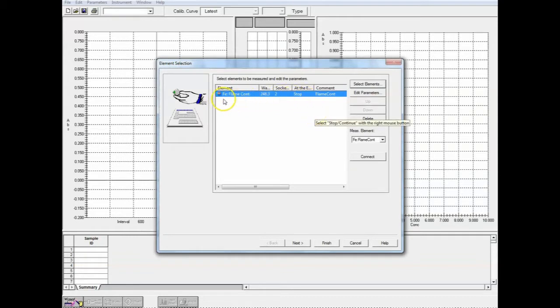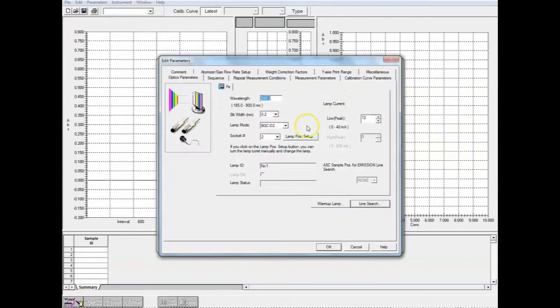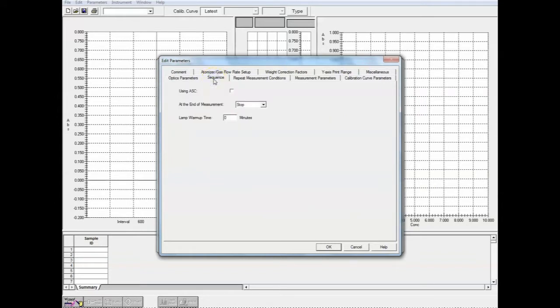So we've selected our element. You can see right here it says iron flame, ready to go. It gives you the wavelength as well. Then we're going to select edit parameters, and that's where we're going to put in the rest of the information about our method. This is where we would be able to change any of the default settings that I showed you previously for the iron lamp. That's all preset. We generally don't need to change any of these parameters for our purposes, so we'll leave that as is, and we'll just go through the rest of the tabs. This one is for ASC, which is an auto sampler. We don't actually have an auto sampler attached to this piece of equipment, so we can ignore that.